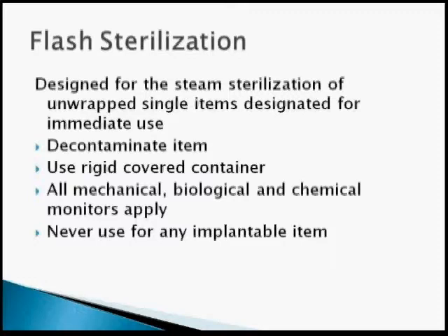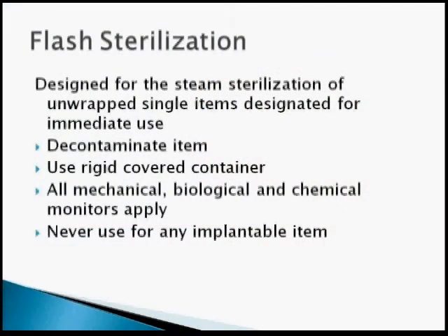I want to talk a little bit about flash sterilization. It is designed for the steam sterilization of unwrapped single items that are designated for immediate use, and it is really recommended that it only ever be used in emergency situations. You have no other piece of equipment available, your patient is ready to go, or you're in the middle of the procedure, and it's more danger to the patient to extend the procedure or repeat it or to alter the procedure in any way than it is to flash sterilize that piece of instrument that you have no other alternative for.